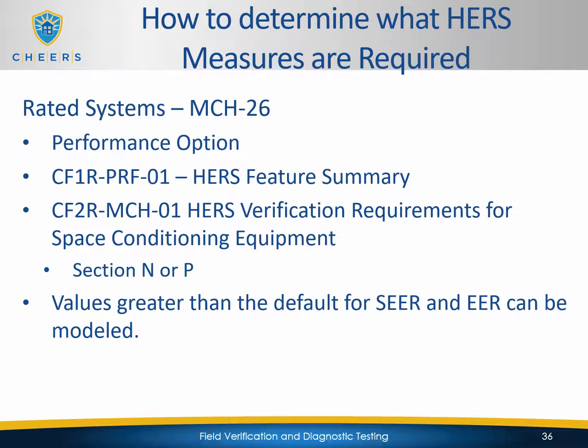So for this one, there are default values, and those are mandatory minimum default values. So when they take this performance option, they have to model values that are greater than the default, and they can do it for either SEER or EER, or both. So what you'll need to do, and we'll cover this in the rated system section, is we're going to show you where you're going to find these modeled values, so you know what those targets are, so you have that for comparison when you do your visual verification.